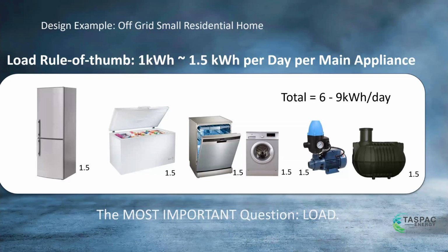And if they say, oh, we want heating, we want to heat the house with a heat pump and we want to do hot water, well you just say to them, look, a normal household power bill is split into three things. Normally it's a third hot water cost and a third space heating in the winter, and the other third is everything else - all these other appliances we've got up here. So if you want to bring in hot water, for instance, your daily load is going to go from 6 or 9 kilowatt hours a day up to probably 20 kilowatt hours a day, and your system is going to double in price just by adding hot water.